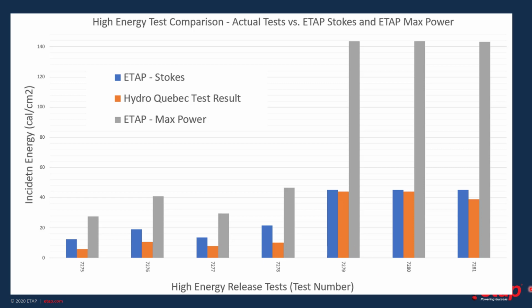So I would classify, as can be seen in this slide, high energy arcs as an arc that occurs in any circuit which can sustain approximately 15 to 20,000 amps or more of fault current. This is very important because arcs with lower currents than that are not going to have such severe ionization and plasma cloud phenomena, which are the causes of most of the heat transfer towards the electrical worker.